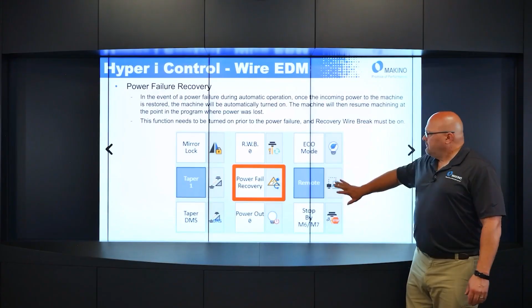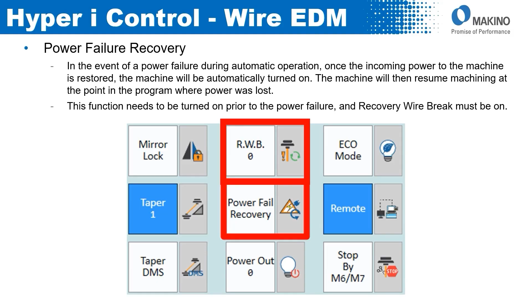Now, for this to work, the function needs to be turned on, obviously, prior to the power failure. So you can see here on the Others page, power failure recovery. If it is white like that, it's not on. If anything's blue, that means that function is on. So you would have to turn that on prior to machining. In addition to that, you also need Recovery Wire Break on. That's right there above it. Normally, Recovery Wire Break is going to be on at all times, so that shouldn't be a problem. So it's a very useful function, especially if you're in an area where you have power drops quite often.